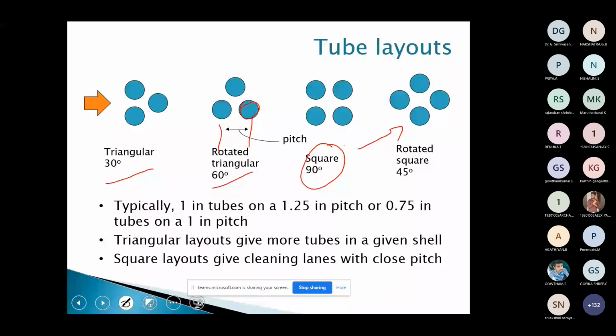So how will you select whether it is a triangular or square pitch? Again, it is based on our requirement. If you want to accommodate a larger number of tubes, which will give you more heat transfer surface area within less space, then we can go for triangular pitch. Triangular pitch can hold a lot of tubes inside a given shell. Whereas if the fluid used is one where fouling occurs frequently, then we have to do the cleaning frequently. In that case, square pitch is preferred because cleaning is very easy in square pitch compared to triangular pitch. So based on these two criteria, we have to select triangular or square pitch.